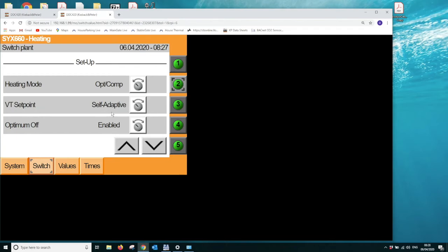This is where we take what we call room influence from the space temperature sensor, which is used for the optimization of the system, and we have the ability to adjust the heating curve or the heating set point by an amount proportional to the difference between the room temperature set point and the current room temperature. So if the room set point was say 21 degrees and the current room temperature was 19 degrees, we are technically under the set point. So what we can do is we can use the VT set point adaptation to increase the current calculated flow temperature to close the gap between the current room temperature and the current room set point.